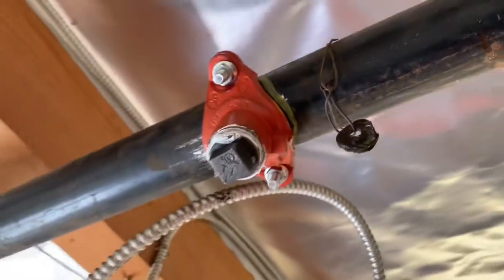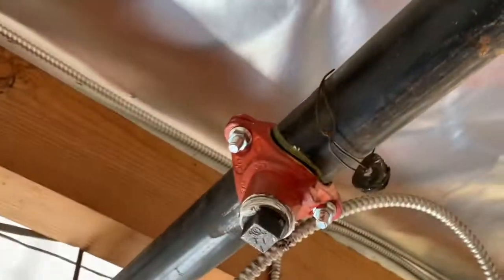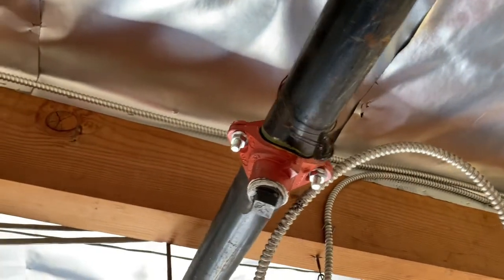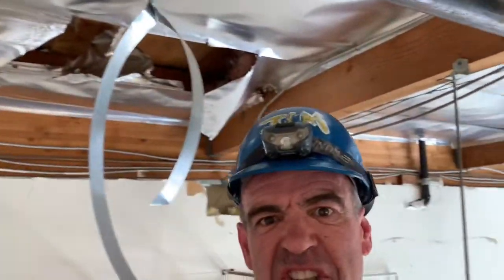There's your new pinhole leak fixed. Whenever you have a pinhole leak, you find out where it's leaking and you just drill a saddle and plug it. That's the easiest way. You can get a repair clamp but those sometimes leak too. One pinhole leak fixed with a side of broken bits — nothing's easy.